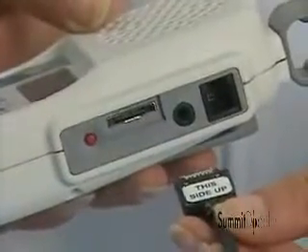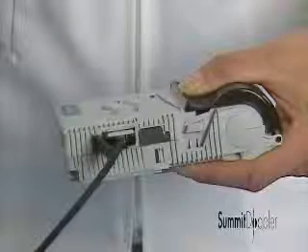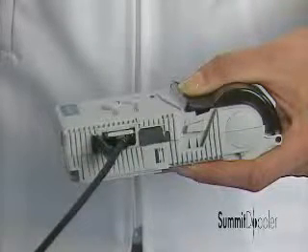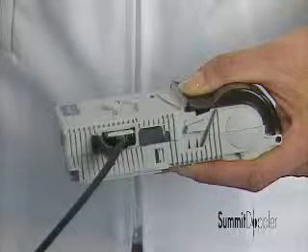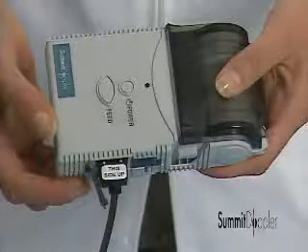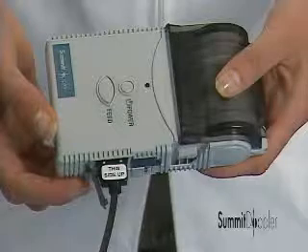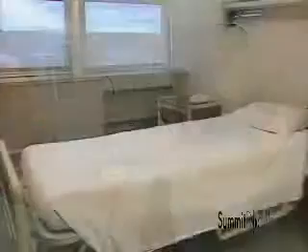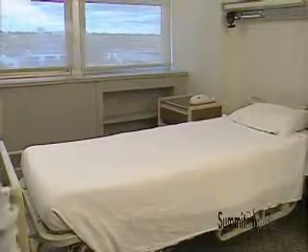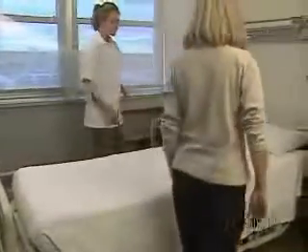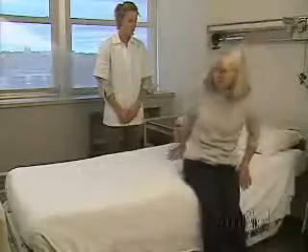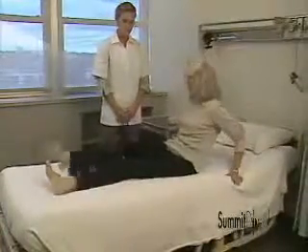The printer cable plugs into the side of the Doppler unit and into the side of the printer. Both ends of the cable are the same, and the cable is labeled to show which side of the connector is up. Press the lever gently to unplug the cable. Prepare the patient for the exam by having them take off their shoes and socks. Ask the patient to rest in a supine position for about 5 minutes prior to taking pressure measurements. You may use this time to discuss the patient's current symptoms, explain the exam, and wrap the blood pressure cuffs.